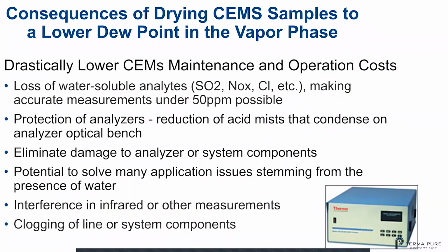So let's go to the next major benefit, which is the consequences of drying CEMS samples to a lower dew point in the vapor phase. And we think this is a big reason why we drastically lower CEMS maintenance and operation costs. As I pointed out to you before, a cooler can really only get down to chilling or cooling and removing water to a dew point of +4. But with a Nafion-based dryer, we can get down to -15 or lower.